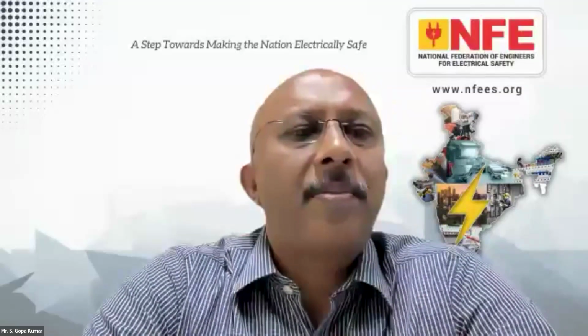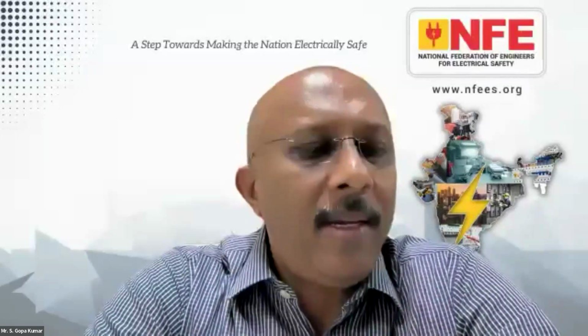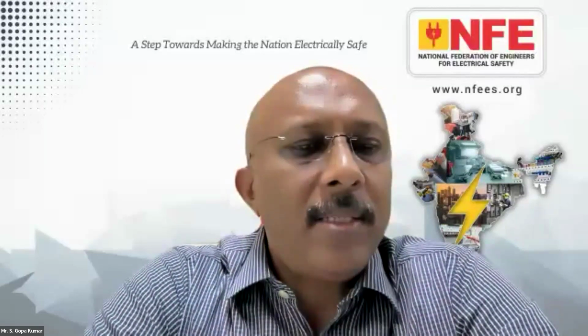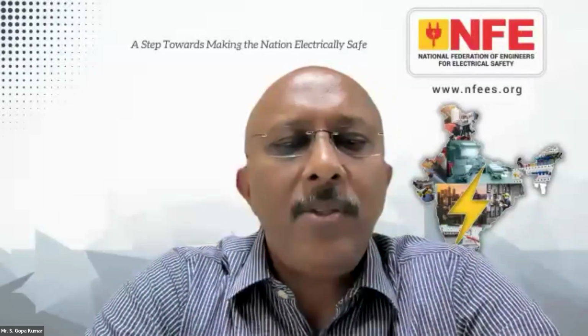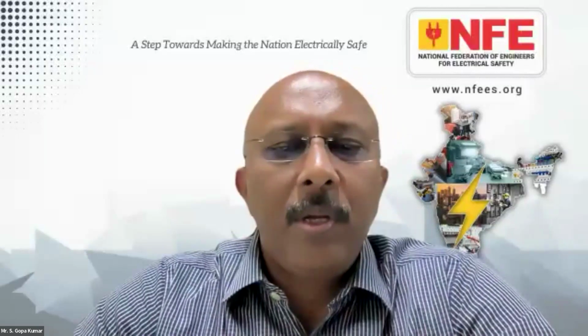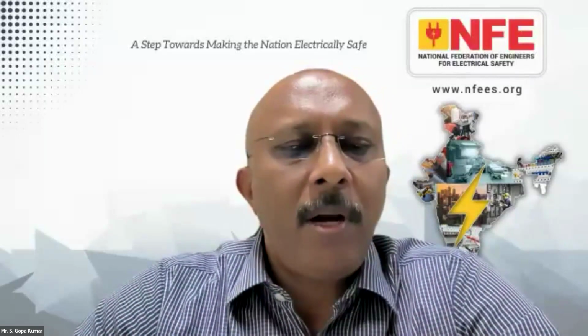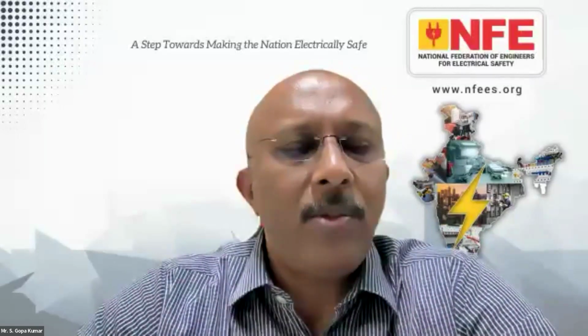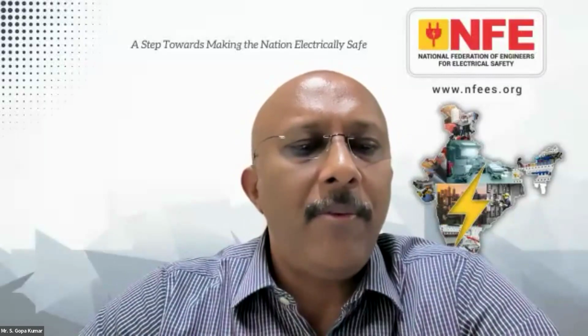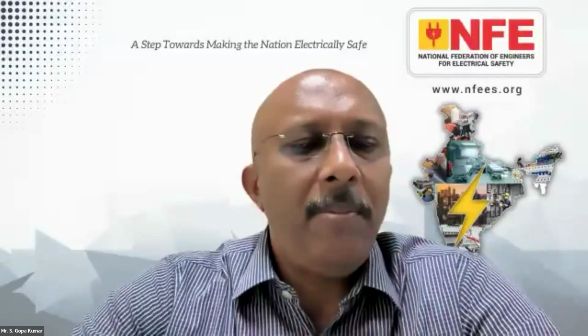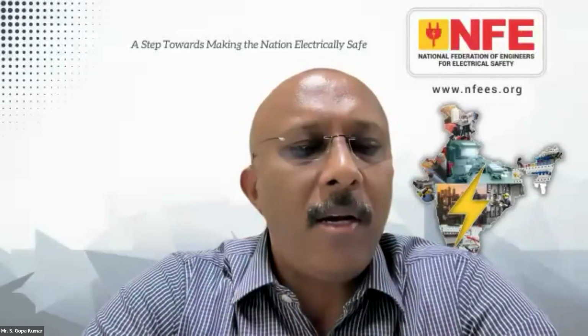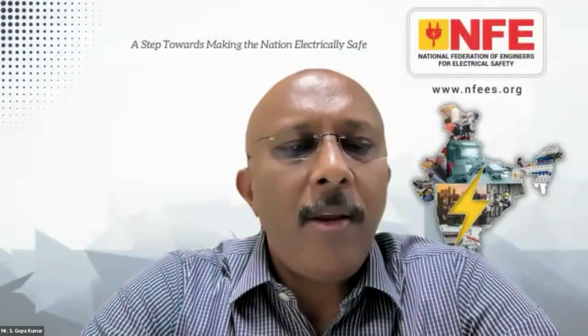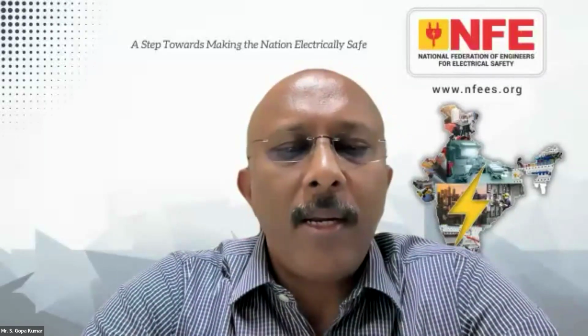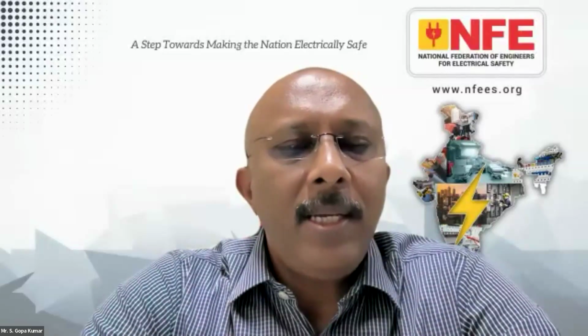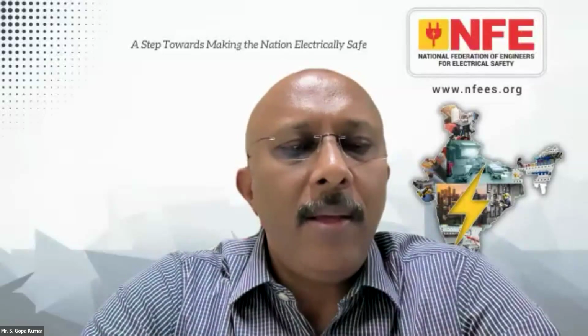May I answer this? Yes. Yeah, Mr. Ramesh, whoever explained this to you is wrong. First of all, 8 SWG wire is not the standard size. You have to size this wire based on the size of the phase conductor. There are certain rules. For example, up to 16 square millimeters, the same size. For 25 and 35, 16 square millimeters. More than 35, half the size of the phase conductor should be the minimum size of this earth fault current return path. During an earth fault, an enormous amount of current flows through this particular conductor, and the conductor has to be sized to handle that current without any temperature rise.